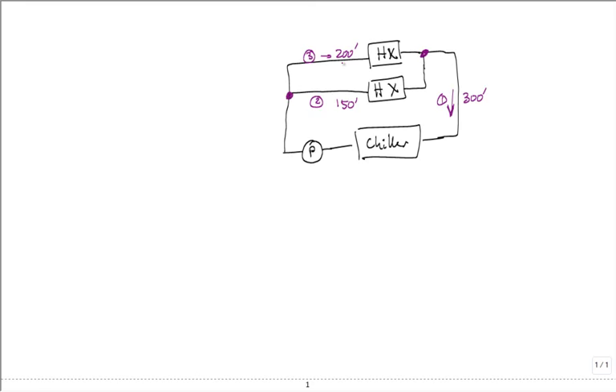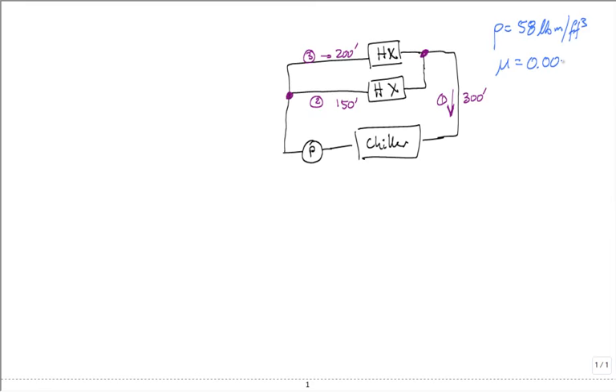How do I calculate major head losses in a straight run of pipe? I would just use f times (L/D) times the velocity head. We're given fluid properties: density is 58 lbm per cubic foot, and viscosity is 0.0013 lbm per foot-second.